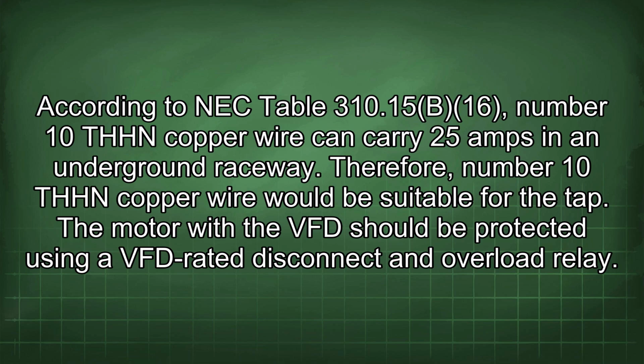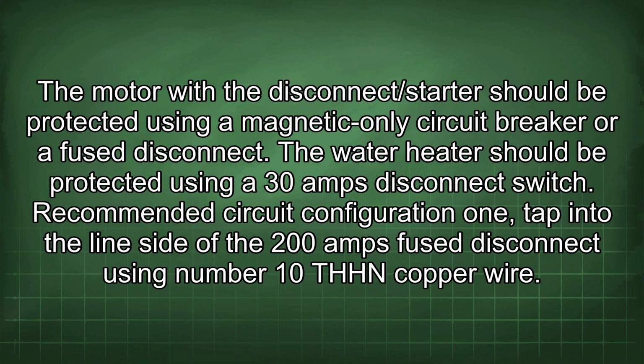The motor with the VFD should be protected using a VFD-rated disconnect and overload relay. The motor with the disconnect/starter should be protected using a magnetic-only circuit breaker or a fused disconnect. The water heater should be protected using a 30 amps disconnect switch.